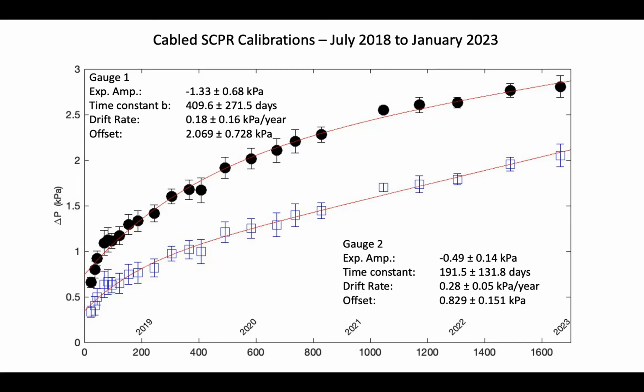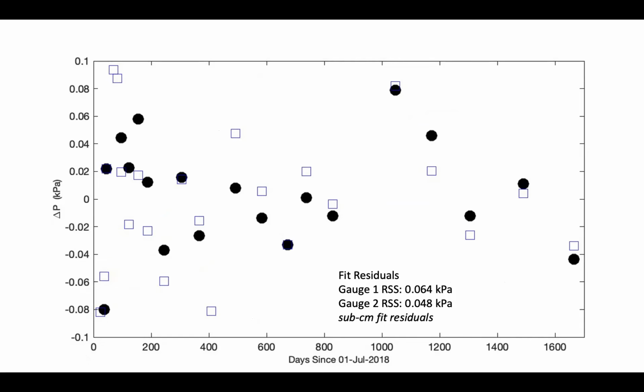We want to look at the residuals. This is what we have. The fit for gauge 1 is about 0.064 kilopascals, about 6 millimeters. The other one is something like 5 millimeters in the residuals here. So they're all following the line. One thing that's interesting is that the gauges are coherent. If they go up, they go down, they go up, they go down, they follow each other pretty well for the most part. What I think that is, is that we're not perfectly monitoring and modeling the dead weight pressure gauge. You might have a little bit of error in the temperature that we're recording with the platinum resistance thermometer. We didn't get quite the hydraulic head right, because we have LVDTs that monitor it. There may be some other effects we don't quite understand. But those calibration pressures are common mode to the gauges. Anyway, the fit of this nice line is on the order of sub-centimeter.